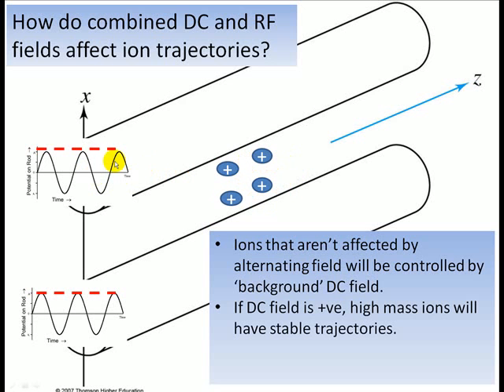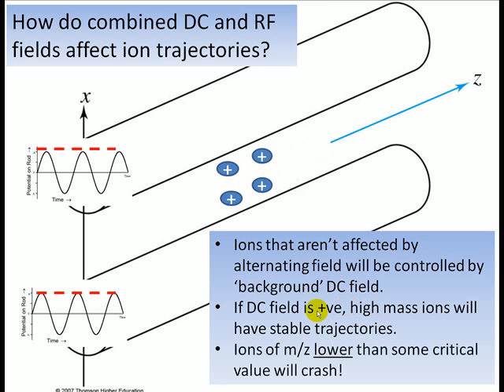They will be controlled largely by the background field, the background DC field, which has the effect of stabilizing their trajectory. High mass ions will have stable trajectories, but if the mass of the ion is too low, lower than some critical value of mass charge ratio, the ions will crash.